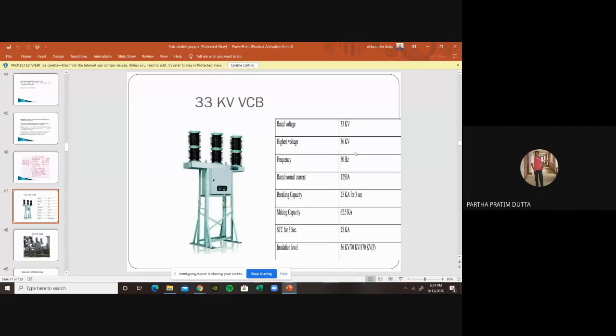Now you see the rated voltage 33 kV, highest voltage 36 kV. And now I just want to cover two things: the breaking capacity and the making capacity. What is the breaking capacity of the 33 kV? At the current 25 kA, that's the maximum withstandable current for this VCB. When 25 kA short circuit or fault current flows through this for 3 seconds, it will break. That means it splits the entire connections and goes to the off position. But the making capacity is much greater than the breaking capacity of a VCB.